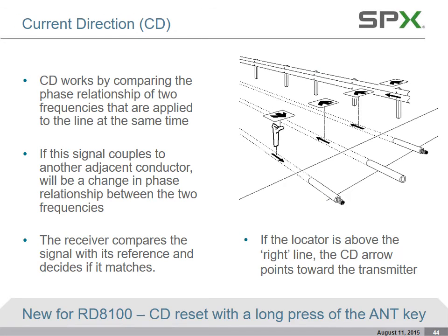The current direction arrow represents the direction that your locate signal is going. So if you get an arrow flipping the opposite direction, you know you're picking up return current going back to the transmitter, and that's probably not the target line you're looking for.